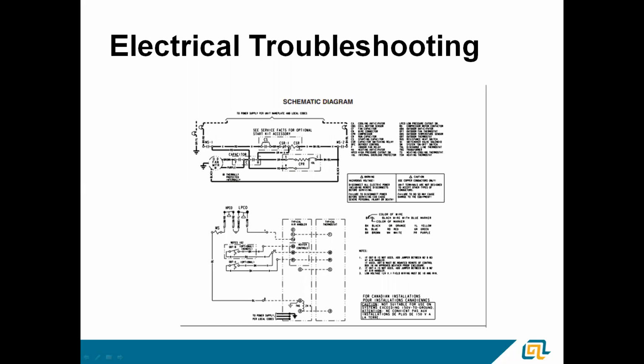Here in the schematic up here, you've got the high voltage. You can see where the capacitor is wired in here. Here's our little start capacitor with that bleed resistor across the terminals. The relay contacts open to drop that out of the circuit. Here's the coil. If you notice, the coil can be energized either right here or right here. Either way, it's going to get power, open those contacts, and take that start capacitor out of the circuit. Very straightforward wiring. Plug in, pretty easy.